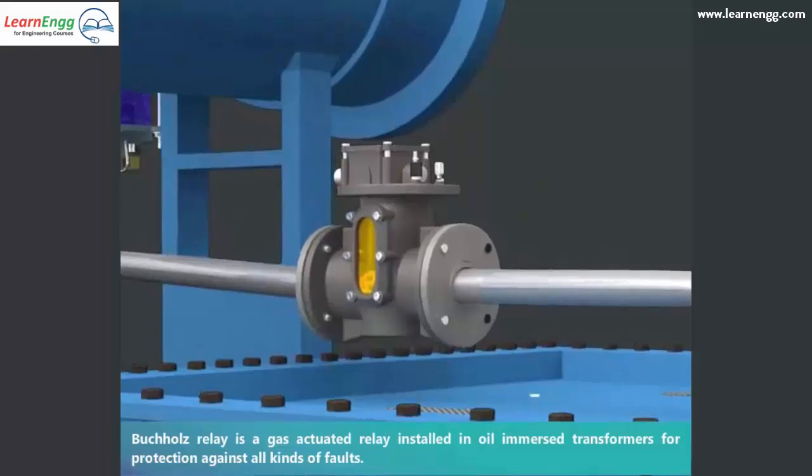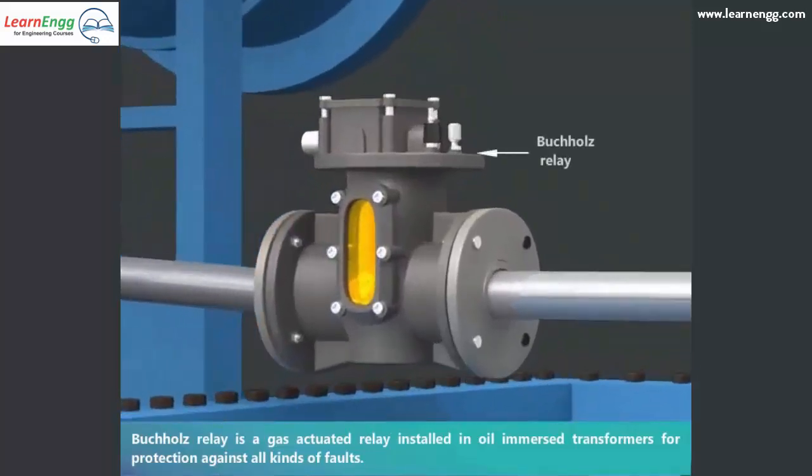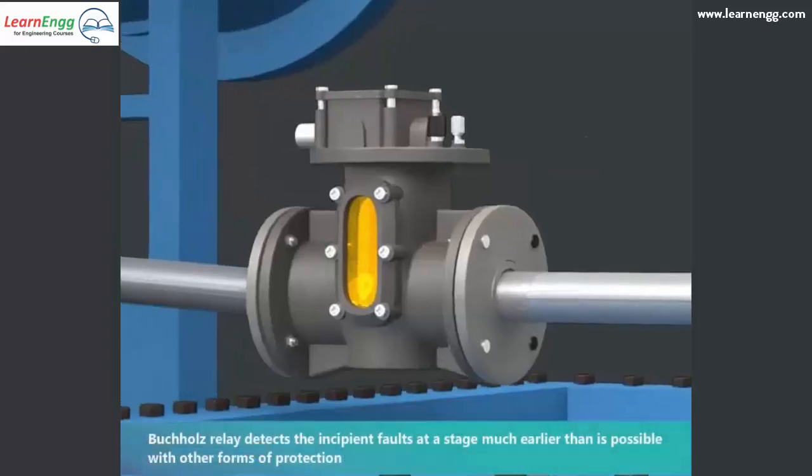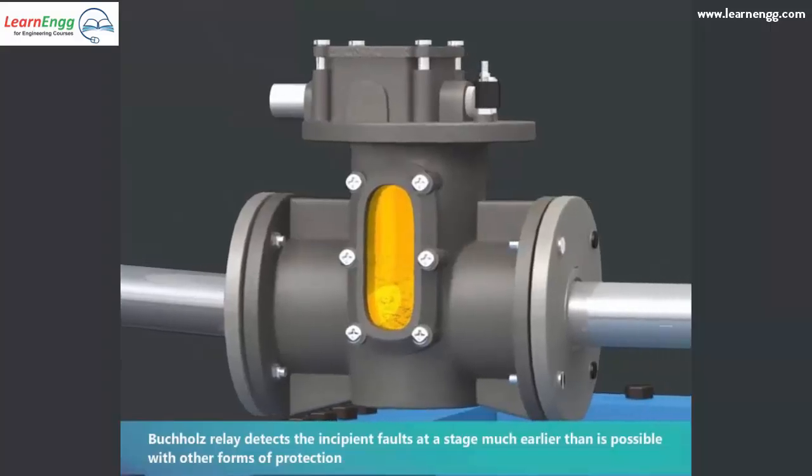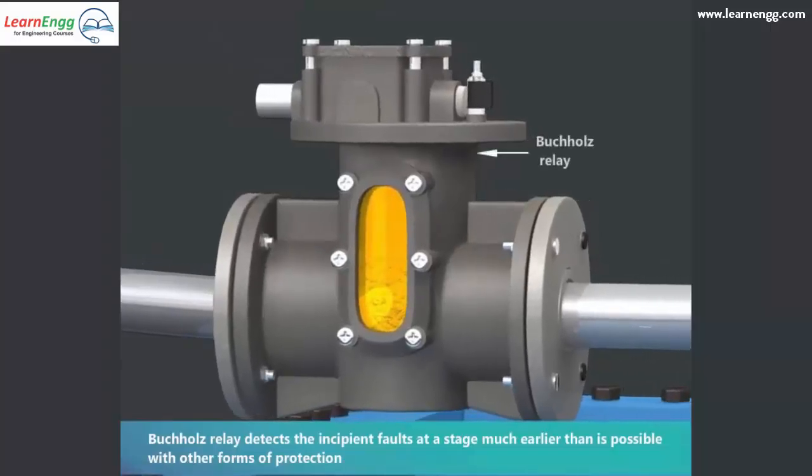Buchholz relay is a gas-activated relay installed in oil-immersed transformers for protection against all kinds of faults. It detects incipient faults at a stage much earlier than is possible with other forms of protection.